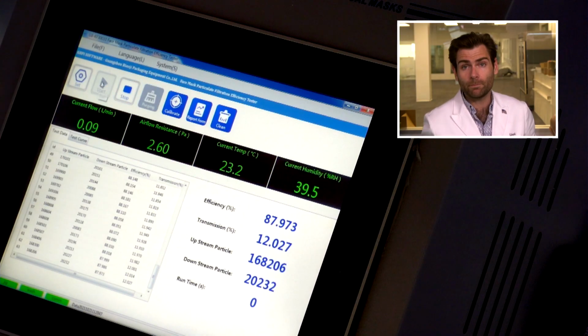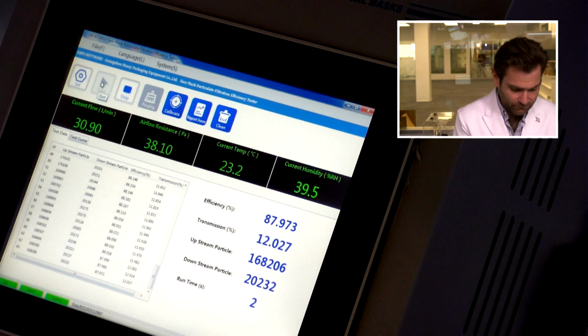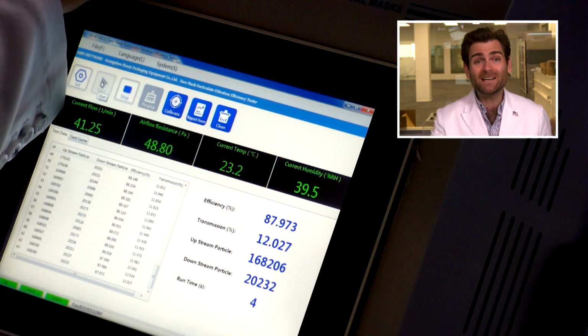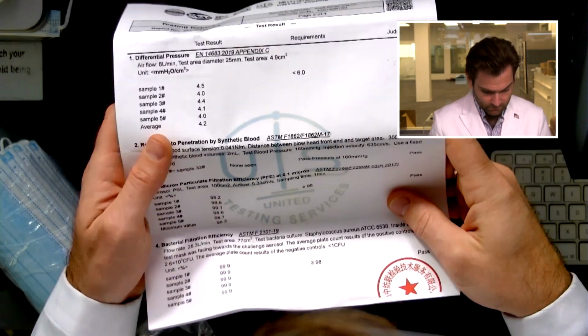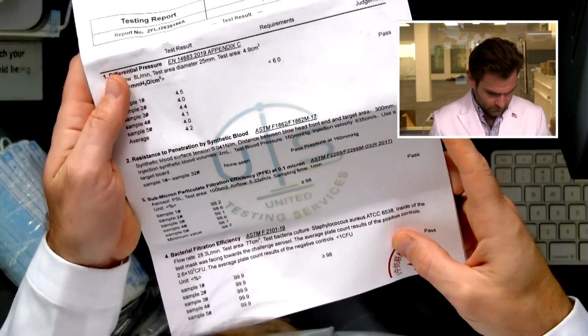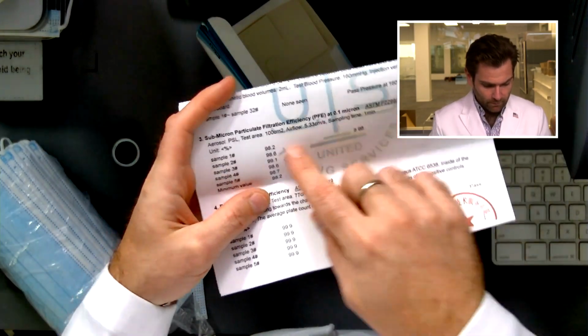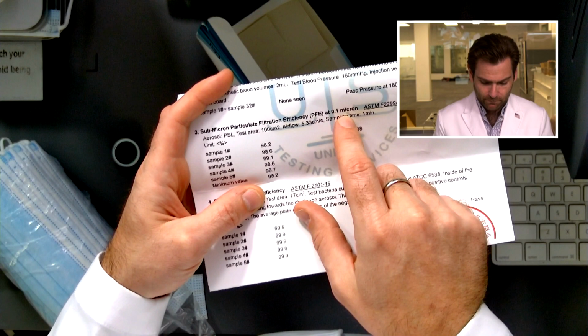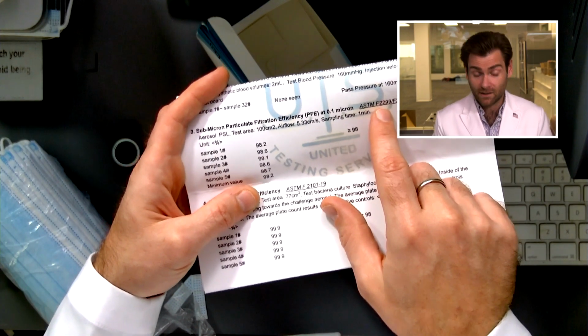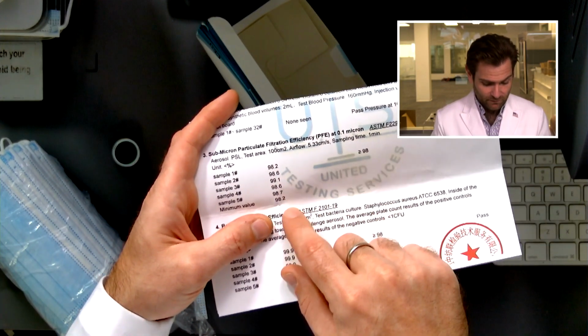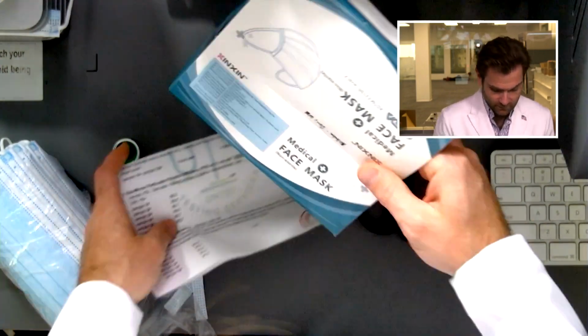Let's let her rip. This is a PFE machine, Particulate Filtration Efficiency machine. To become an FDA mask, you have to pass this and 7 other tests. I'm not going to do a blood splatter test, although I could. It's right there. That's one of the tests. Look at the report that they sent me. So submicron particulate filtration efficiency at 0.1 micron. This is the F2299 test. They're claiming 98% that they've made it.